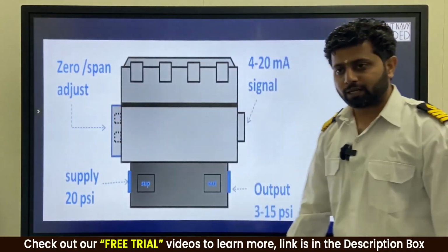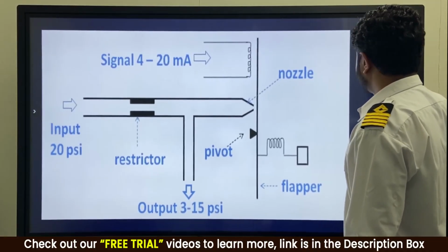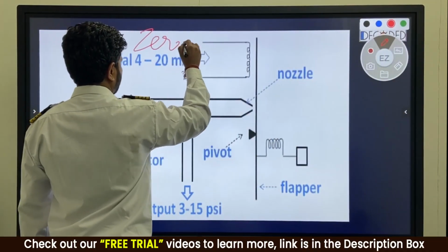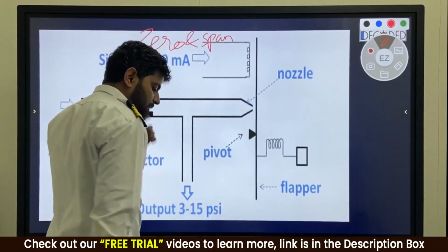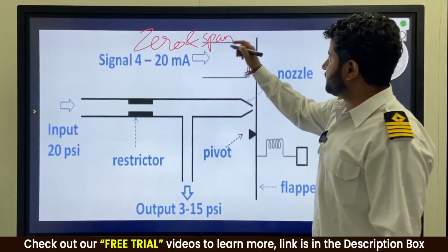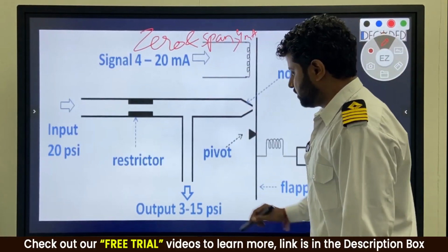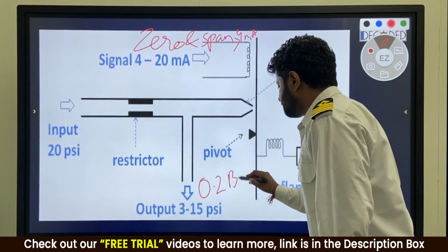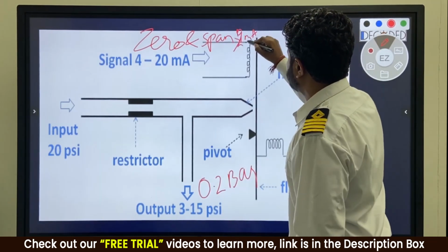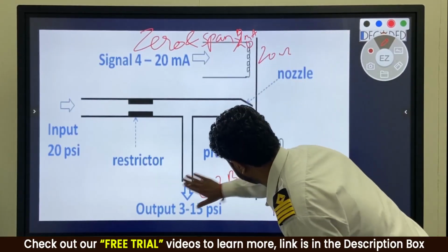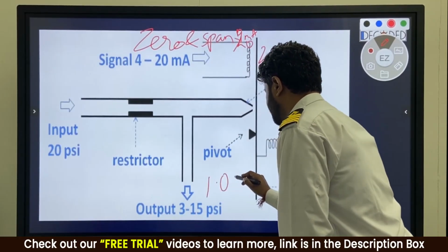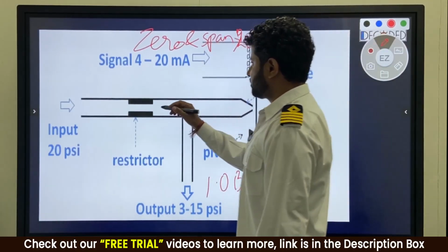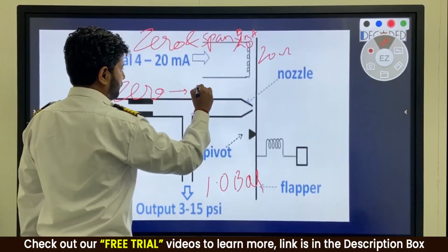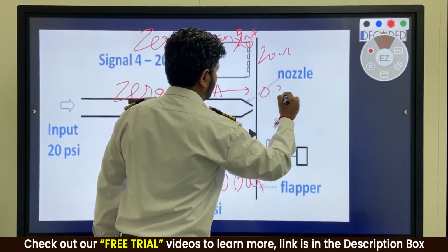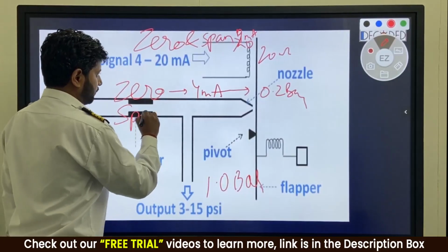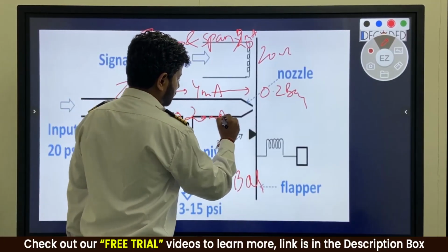What is zero and span adjustment over here? What does zero and span adjustment mean? Zero and span means we have to ensure that when 4 milliamp current is flowing, the output is 0.2 bar, right? And when 20 milliamp current is flowing, the output is 1 bar or 15 psi. So the first one, zero: 4 milliamps, output pressure 0.2 bar. Span: 20 milliamps, output 1 bar.